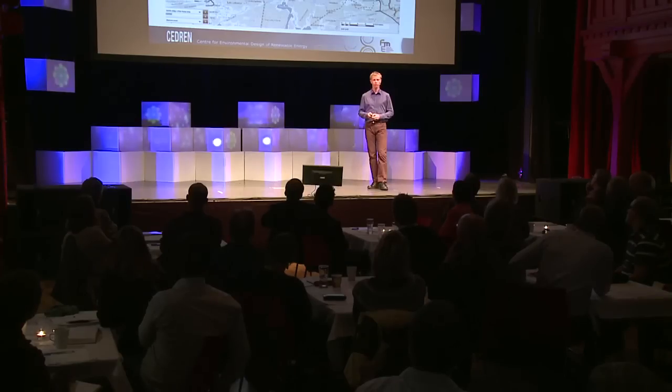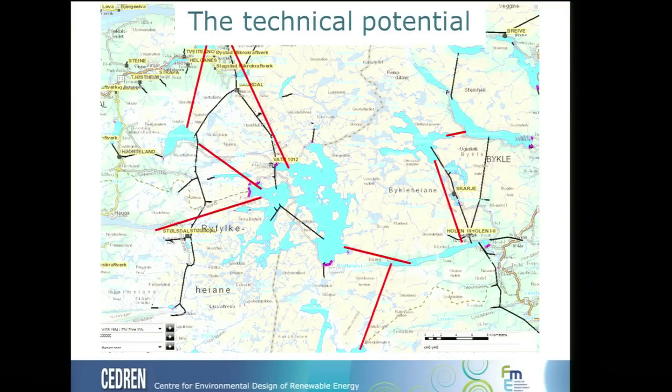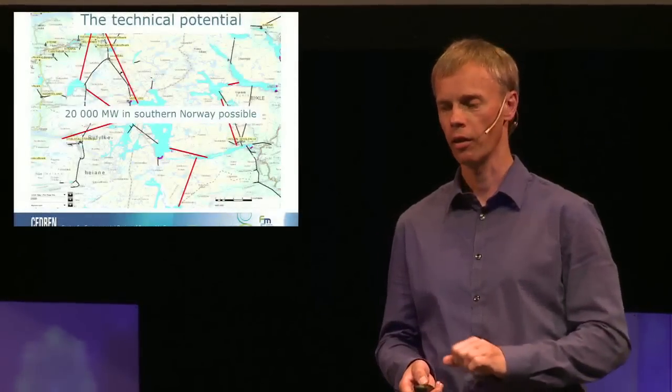At CEDREN, the research center — a combination of Sintef, NTNU, and NINA — we have looked at the technical potential in a preliminary study. We went into the map: the blue areas are reservoirs and the black lines are existing tunnels and hydropower plants. We checked the possibilities to install in parallel and calculated feasibility with preliminary design, showing it will be fully possible to develop around 20,000 megawatts of balancing power in southern Norway, without any new reservoirs and without dramatic change in water level — around 10 centimeters per hour as a maximum limit. This could feasibly be developed by around 2030 or 2035.